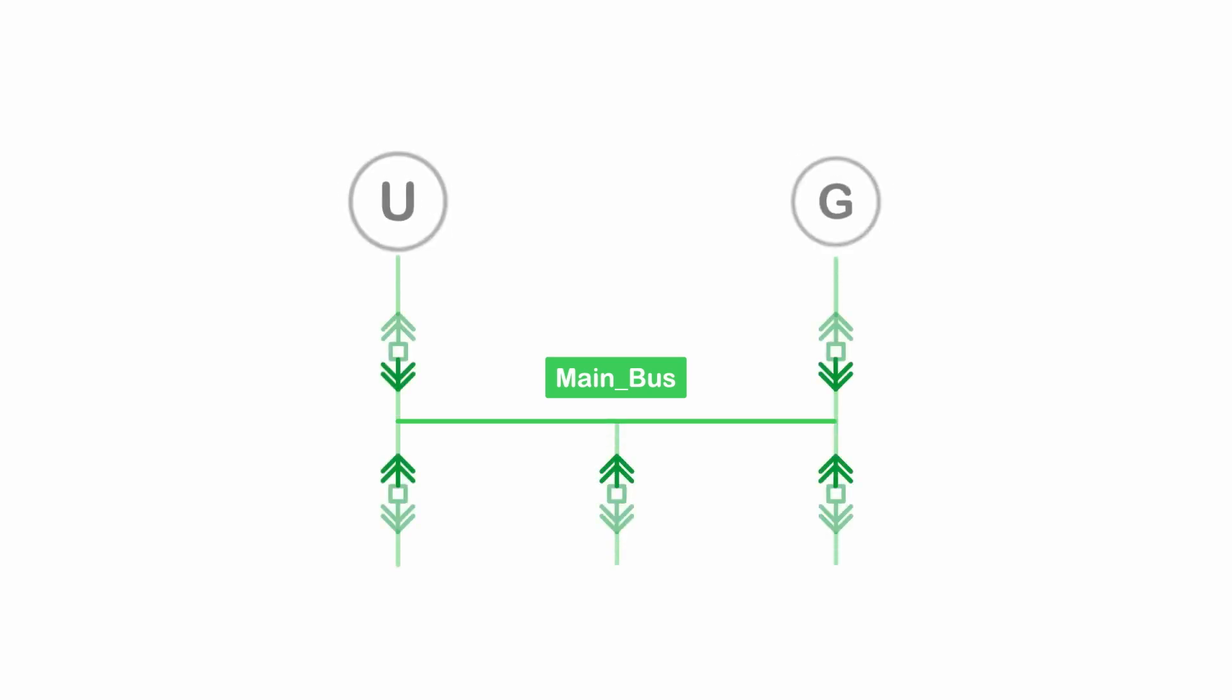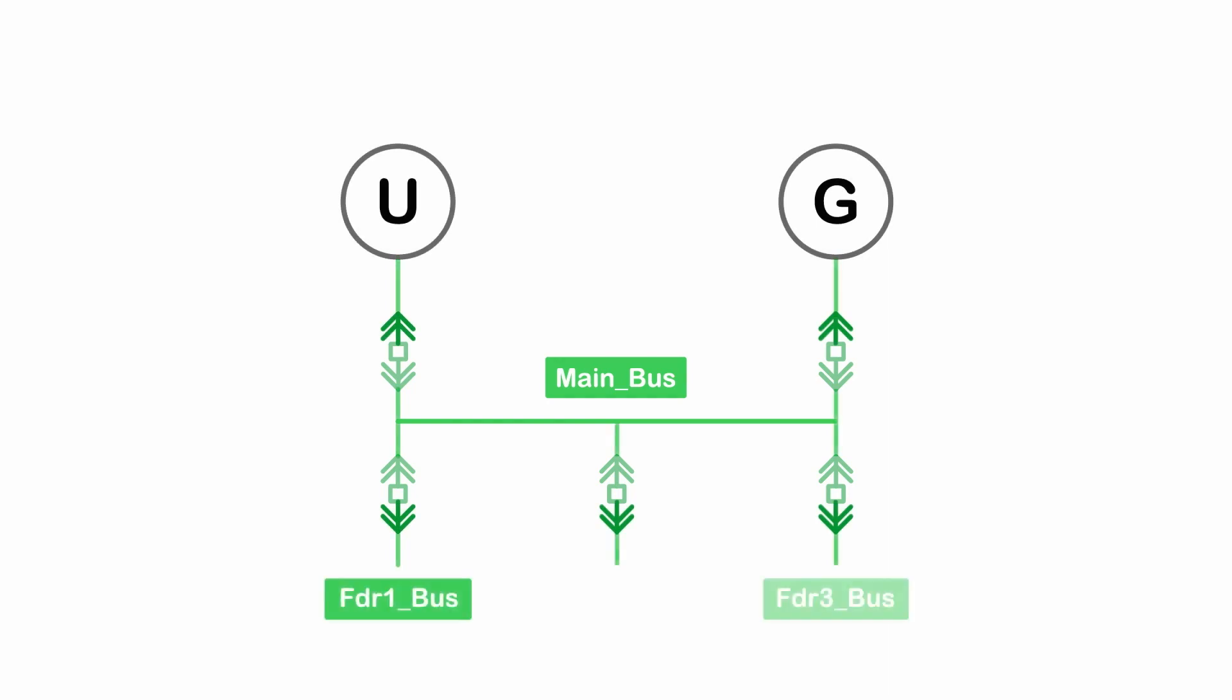If I have an entire double ended switchgear, the entire main bus, the outputs of the main breakers, and the inputs of the feeder breakers will all have the same bus name. However, the other sides of the breakers will all have unique bus names. Understanding how these buses work electrically is critical to the advanced one line logic.